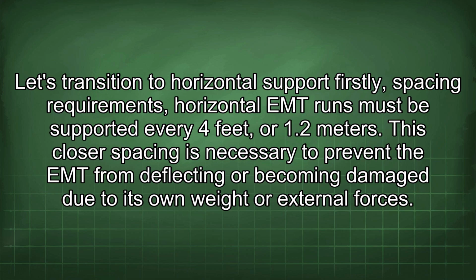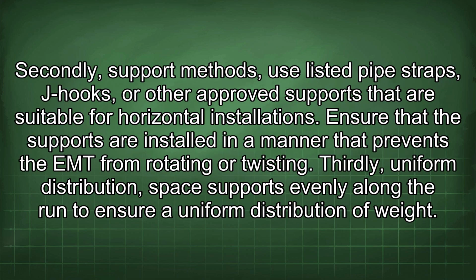Let's transition to horizontal support. Firstly, spacing requirements. Horizontal EMT runs must be supported every 4 feet, or 1.2 meters. This closer spacing is necessary to prevent the EMT from deflecting or becoming damaged due to its own weight or external forces. Secondly, support methods. Use listed pipe straps, J-hooks, or other approved supports that are suitable for horizontal installations. Ensure that the supports are installed in a manner that prevents the EMT from rotating or twisting.